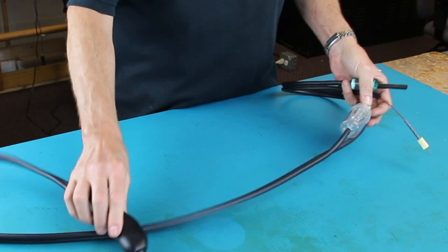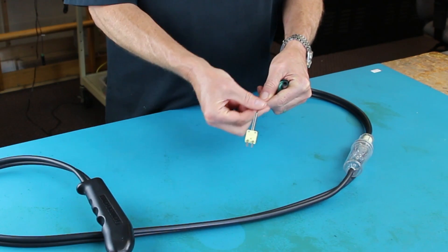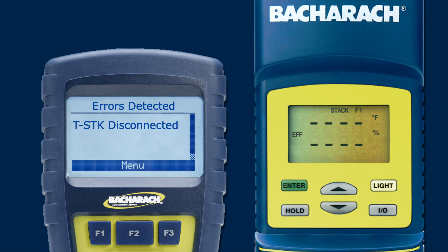The probe assembly has a yellow thermocouple connector on the end of the brown thermocouple wire. During normal use, the thermocouple wiring inside the connector may become loose, shorted, or even broken, causing a T-Stack error on the InTech analyzer or a blank T-Stack reading on the Fyrite Tech 60 and Tech 50. In either case, it indicates a problem.